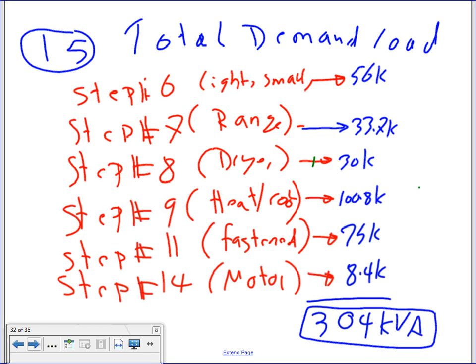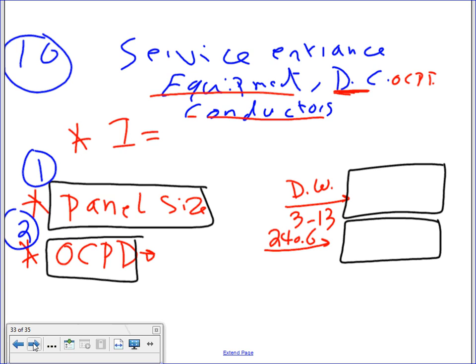All right, let's go size now. Any questions, guys? Any comments, questions? Almost done, like I said. Okay, we're going to go size. Now, service entrance equipment, disconnect, overcurrent protection device, and conductors. The first thing you need to do for this baby is take the 304K divided by 240 to find the amps. That will get you a healthy 1267 amps.